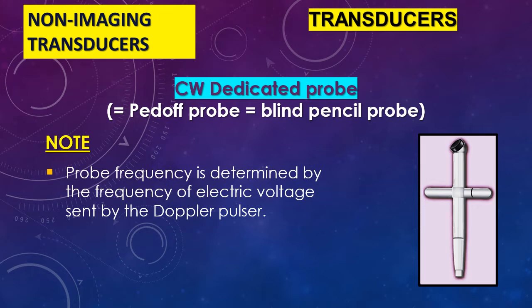Why? Because I don't want to damp the transmitted waves. I want them to be in a continuous transmission. Since we don't have a damping layer, there is no imaging. It's a non-imaging probe. It's narrow band, it's high Q and high sensitivity. All of these come as a bundle. As far as we have no damping layer, I will have these come together as a bundle.